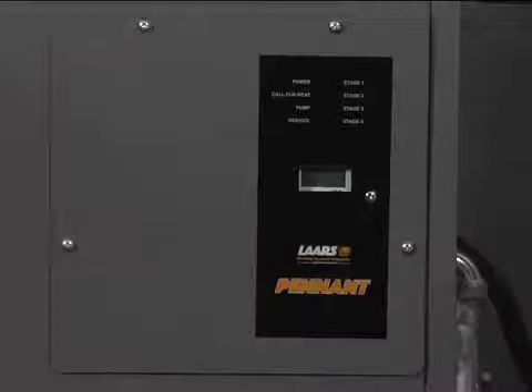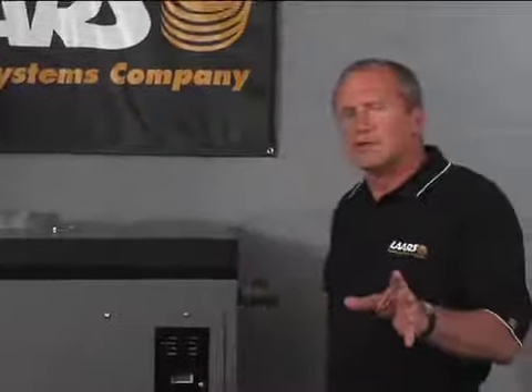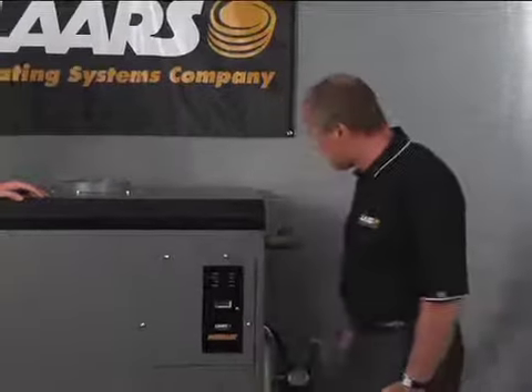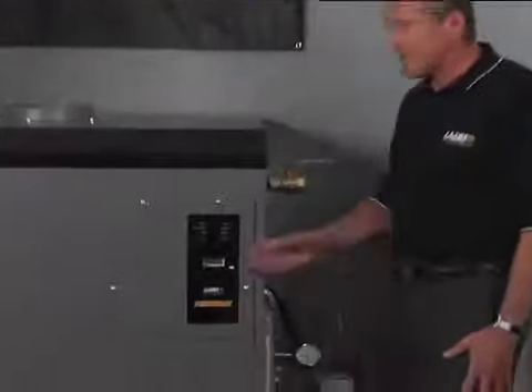And with that, there's a few more things you should know about the Pennant. This product can also be utilized as a pool heater. And when we utilize this product as a pool heater, we put in a bypass assembly in the front part of this header here that's tied into a control that automatically controls the temperature in the heat exchanger so we don't condense, because pool water temperatures are a lot lower than what this boiler will accept, and so we control that automatically. We also can provide other heat exchanger options, which Tom will speak to.